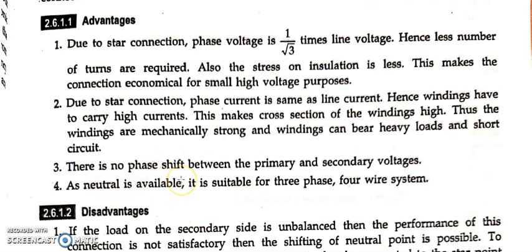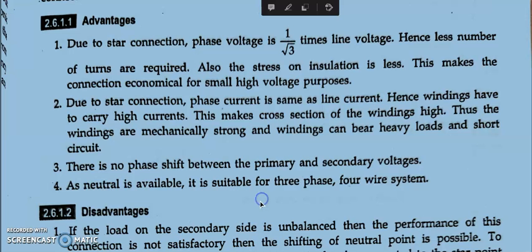Again, there is no phase shift between primary and secondary side, like we saw, since both were in star, so there is no phase shift. As we have neutral here, it is suitable for single phase purpose, as well as suitable for 3-phase 4-wire system. Both.